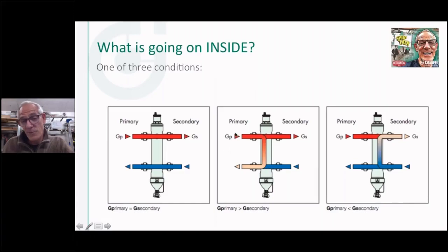So you can see, obviously, if we've got 40 gallons per minute flow coming in and only a 30 gallon a minute demand on it, some of that flow is obviously going to go back down through the separator and back to the boiler, and you're going to get a blending of temperature here. Now, you might not want that, because if I had a ModCon boiler over here, I'd like to have the coldest water coming back to it. But obviously if my flow rates aren't the same, I'm going to be blending up that return temperature. Let's say it's coming in here at, pick a number, 70 degrees, and blending some of the hot water with that 70, and I'm blending the return going back to it. It's the way it is when you mix two fluid streams at different temperatures and different flow rates, they're going to blend. There's really no way around that.